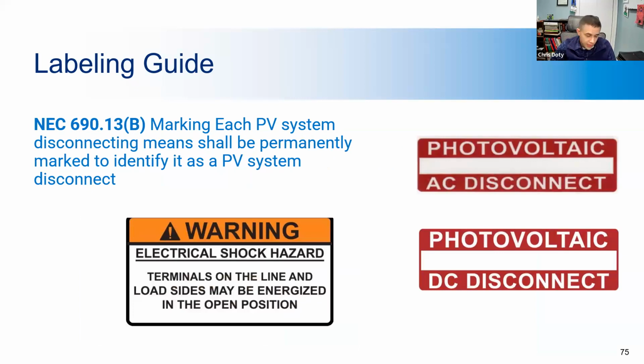So here we have PV AC and DC disconnect labels. You definitely want to have a label on the PV system disconnects, and you're also going to want the electrical shock hazard labeling. Traditionally, if you shut down the disconnect to a system, the power will just be off. But if you shut off the main disconnect and not the solar disconnect, if the sun's out, you'll likely still have an energized system, and you definitely want to make that clear. And just remember, labels have to be suitable for the environment in which they're installed, and should be expected to last the life of the system. And again, a missing label is bad, a wrong label is even worse.